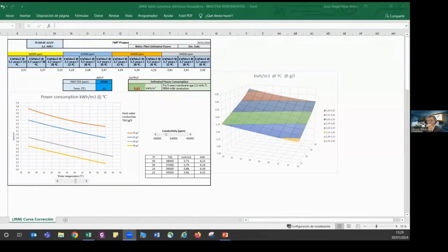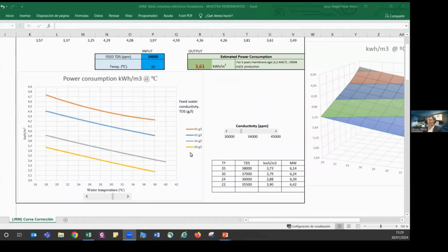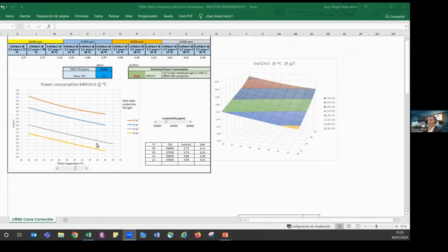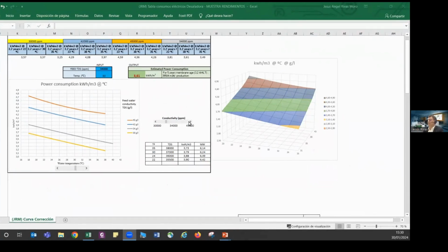Yes, now we see the Excel. Okay, you see that. Okay, much better now. These graphics, these correction curves, are what the EPCs can prepare. You have at the end to calculate the estimated power consumption, in this case 3.60, depending on the TDS and temperature of the water. If you increase the conductivity, for instance, you see here the green line, the gray line moves, and the calculation the same.